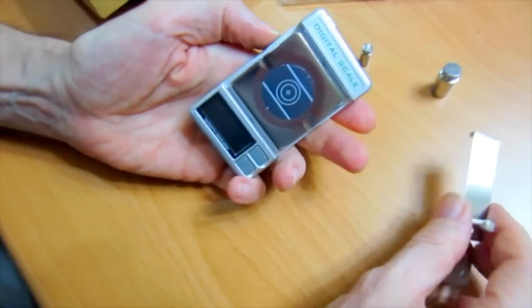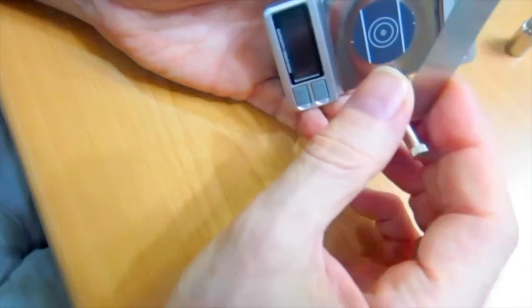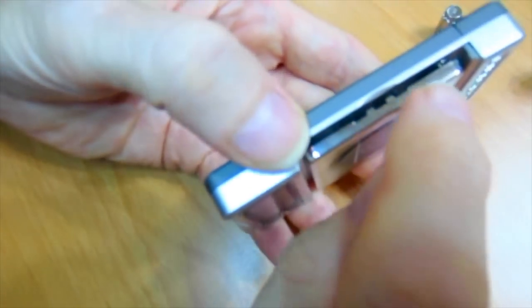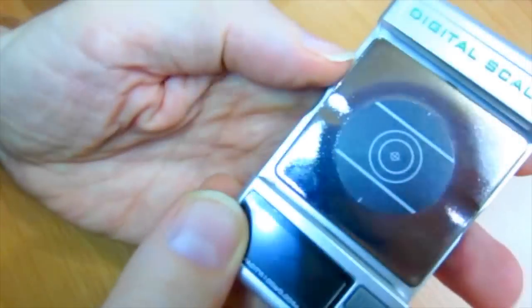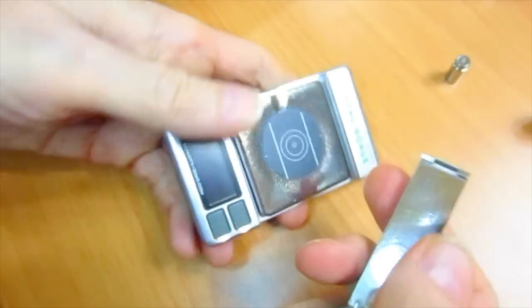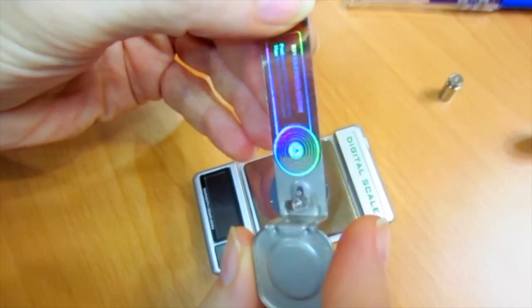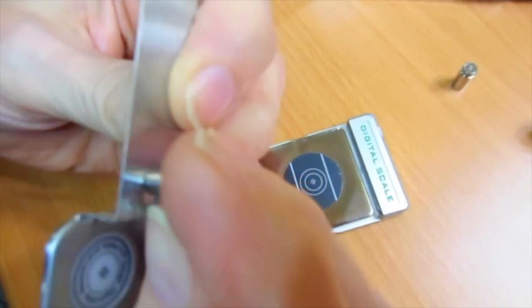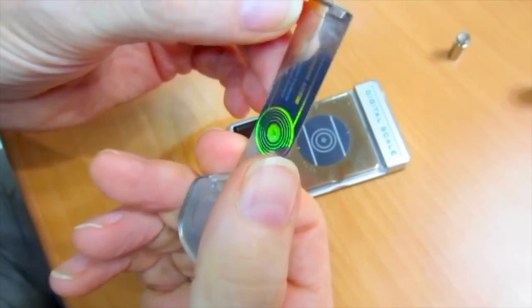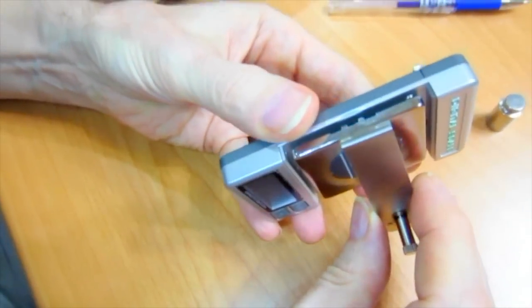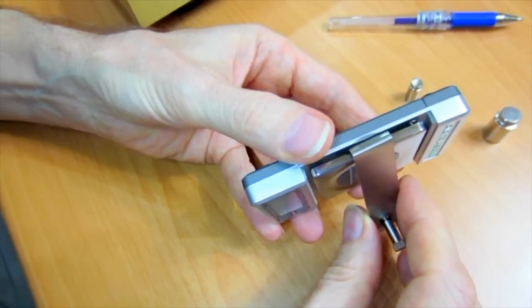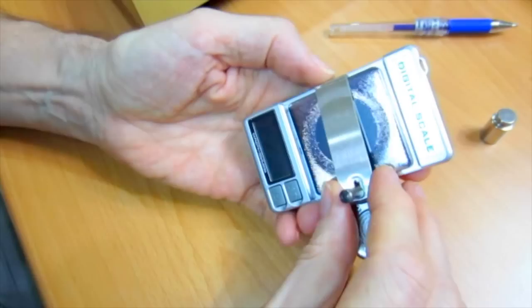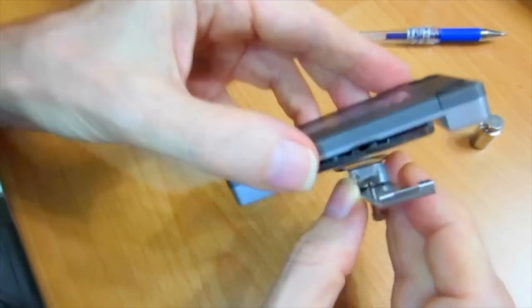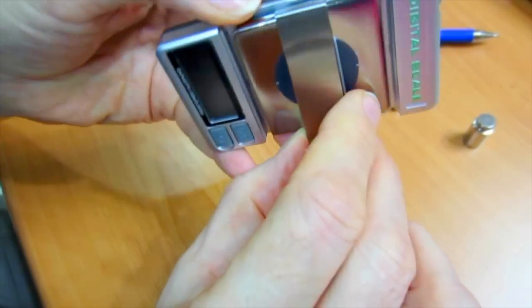Let me go ahead and show you how the extension arm is attached, and let's calibrate it with the extension arm on. You'll notice, if you look at the central loading platform, 3 slots on both sides. And on the extension arm itself, you'll notice 2 tabs on one end. You also notice at the end of this screw another tab. Alright, and so these mate with the slots that are in the pan. All right. And what you typically would do, now it's more logical probably to put it on this side of the scale. All right, so I'll align these two tabs with those two slots and gently rotate.